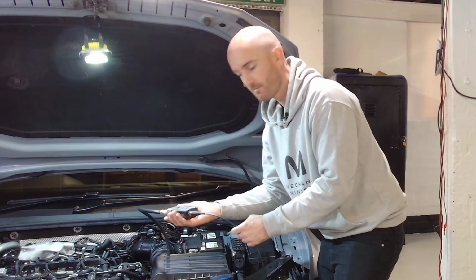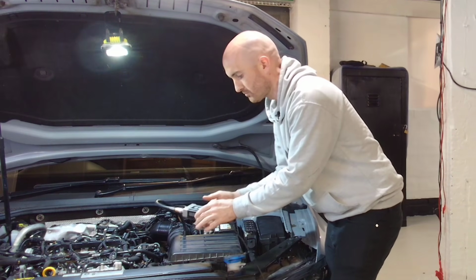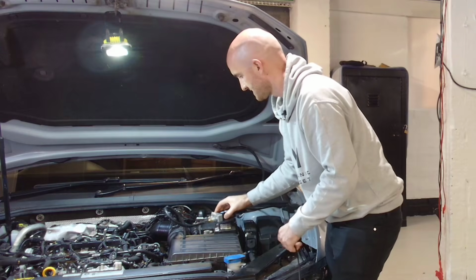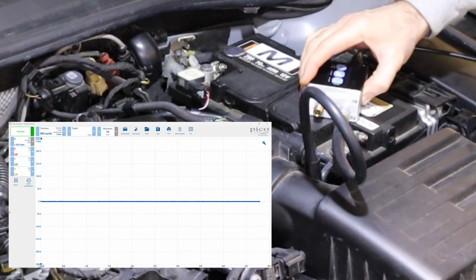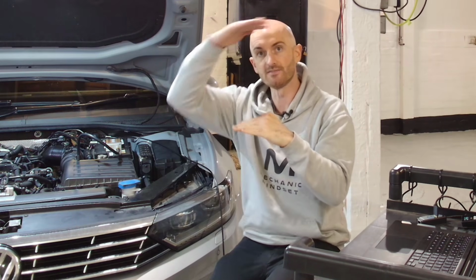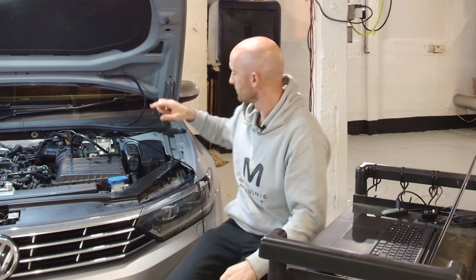The other great benefit of using the WPS500 pressure transducer for this test is that it's not susceptible to vibrations like a normal pulse sensor. The other thing with a pulse sensor is that because it works with a piezo crystal, there's a reaction for every action - so if you increase the pressure, the signal goes back down again even though the pressure is still held high. With the WPS500, you're going to read whatever pressure reading you get without those reactions.